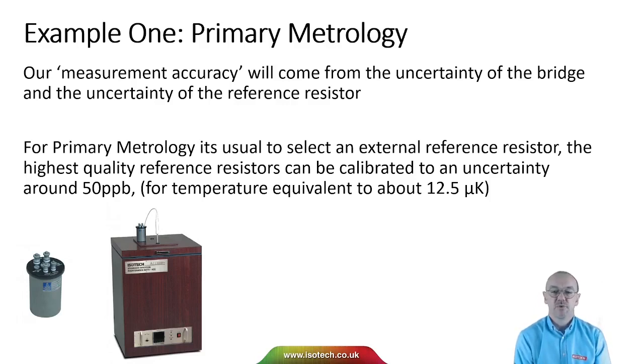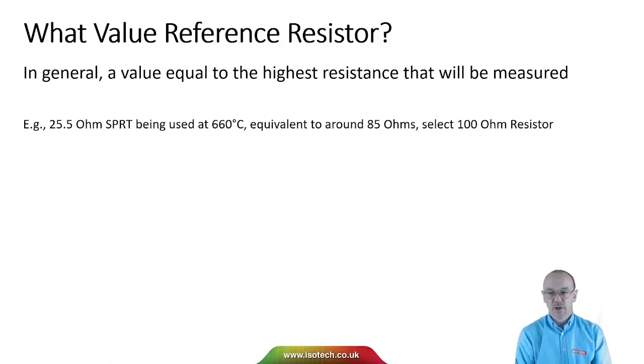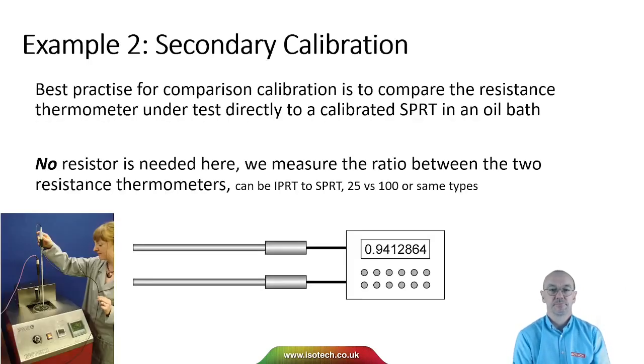They can be calibrated to uncertainty of around 50 parts per billion, the temperature maybe 12.5 microK. And I want to temperature control that reference resistor. So that's the example for primary metrology. What value should it be? With the MicroK in general, we would say a value equal to the highest resistance that we measured. So for a 25 ohm SPRT, if we take that to the aluminium point at 660, that's equivalent to about 85 ohms. So we could select a 100 ohm reference resistor.